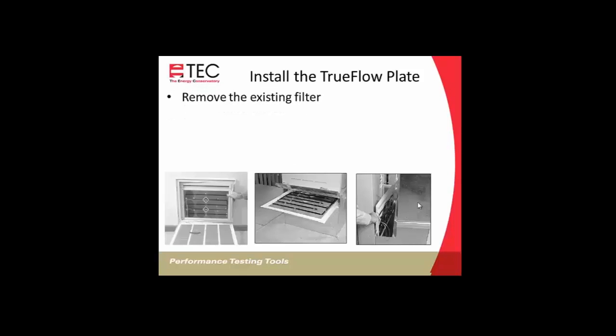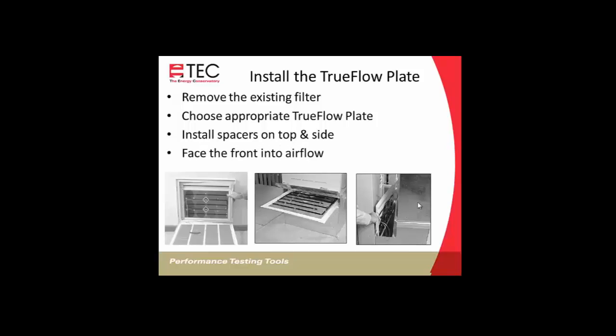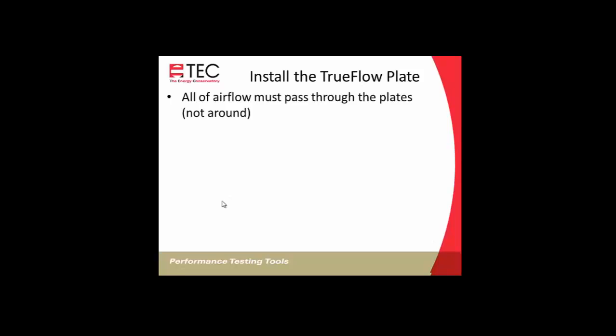So you'll remove the existing filter, choose the appropriate TrueFlow plate. You'll add the spacers top and side as needed, and you want to face the front into the airflow. And the front is defined as the side that has the two diamond-shaped Energy Conservatory stickers on it. You want that to point into the airflow. It's important that all the airflow must pass through the plates and not around the plates. And all the air must also pass over the plate.